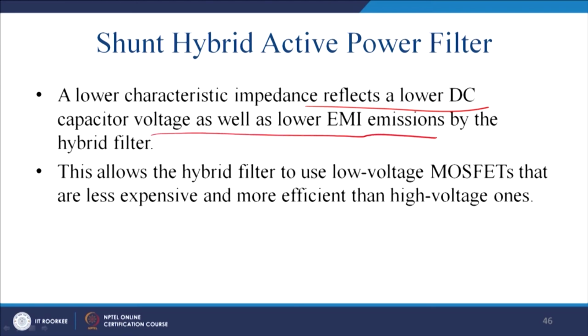as well as lower EMI emissions by the hybrid filter. This allows the hybrid filter to use low voltage devices, because the rating comes down to only 1.6 kVA. Low voltage MOSFETs are less expensive and more efficient than high voltage ones, because their conduction losses are quite low compared to IGBTs, and the turn on and turn off losses are also quite low. For this reason, overall efficiency also improves with the MOSFETs.